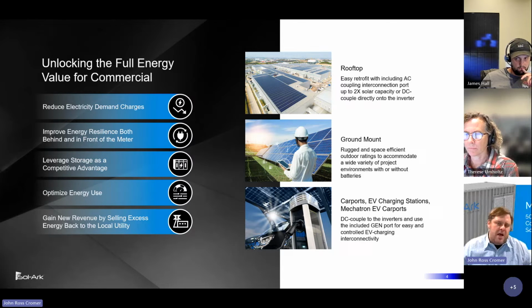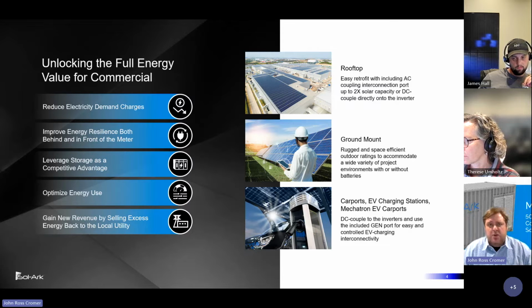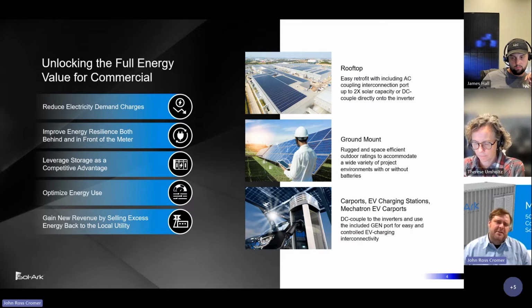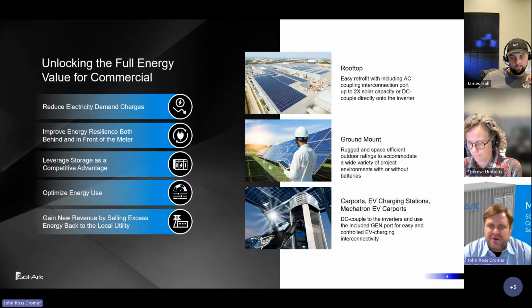And so let's say you've already done a megawatt sized commercial rooftop solar array. You want to go back and add batteries to it. That's a very easy project with Sol-ark. With other inverters, if you had a 1 megawatt solar array, you would have to AC couple a 1 megawatt battery inverter system. With Sol-ark, you could get away with around a 650 kW or 600 kW battery backup system. So the battery backup system can be undersized relative to the AC coupled solar, and that just might create the budget flexibility you need to incorporate some battery retrofitting.